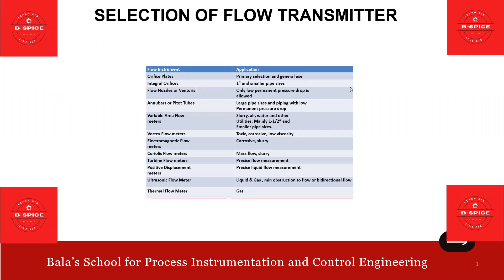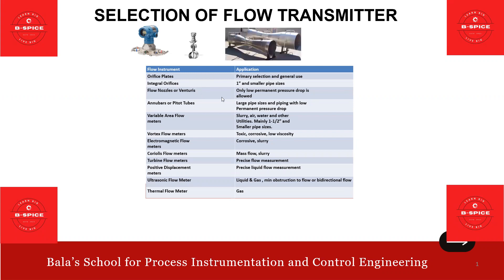Orifice plates: the differential orifice is the primary selection and generally used. Integral orifice is used for line size 1 inch and smaller pipe size. Flow nozzle or venturi is used when only low permanent pressure drop is allowed. Annubar or pitot tube is used for large pipe size and piping with low permanent pressure drop.